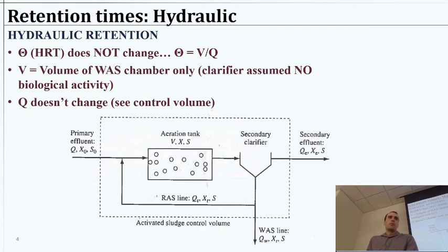So that kind of brings us to the concept of hydraulic versus solids retention time. So hydraulic retention time is a little straightforward. Some of the assumptions we made earlier are going to come into play here. We've talked about hydraulic retention time quite often. That's theta equals V over Q.